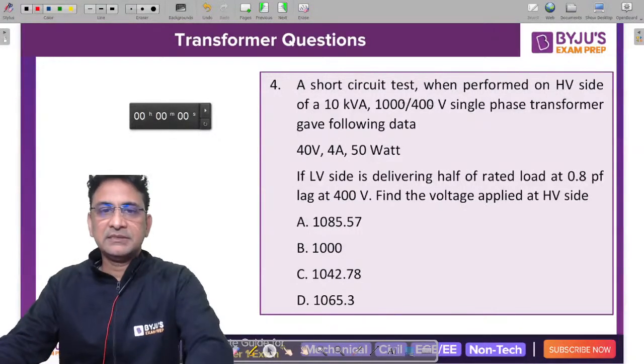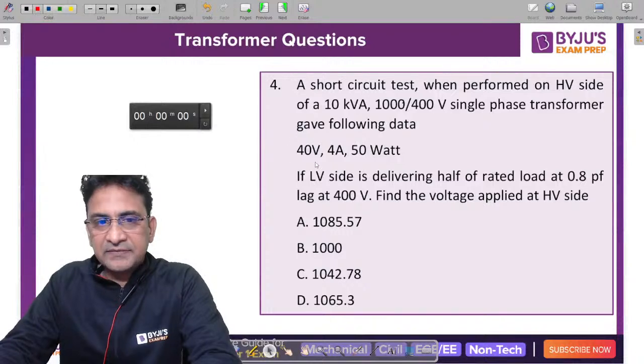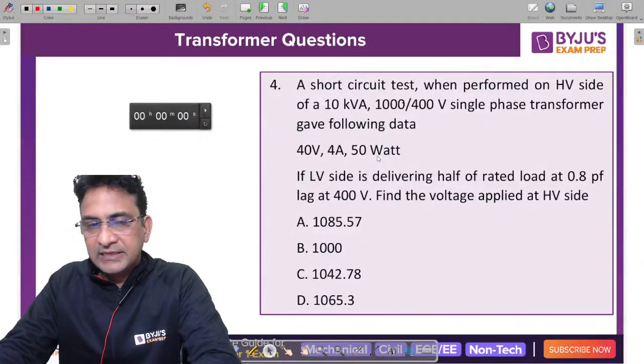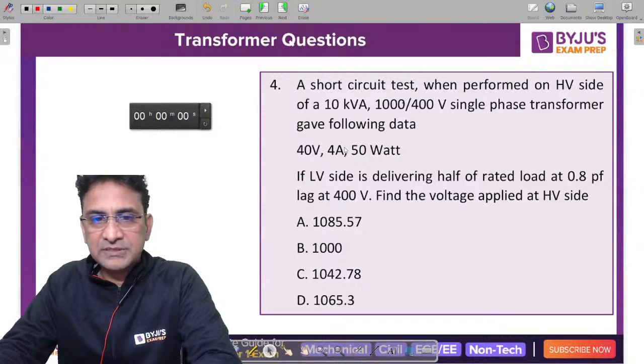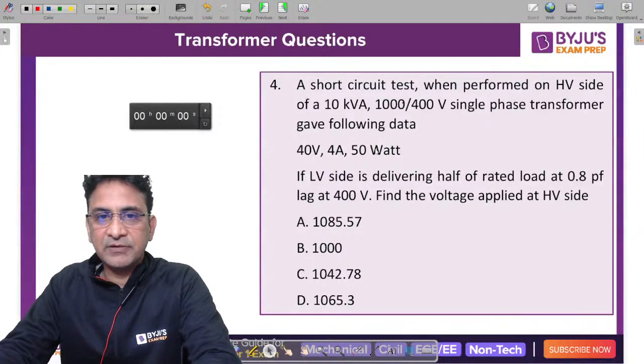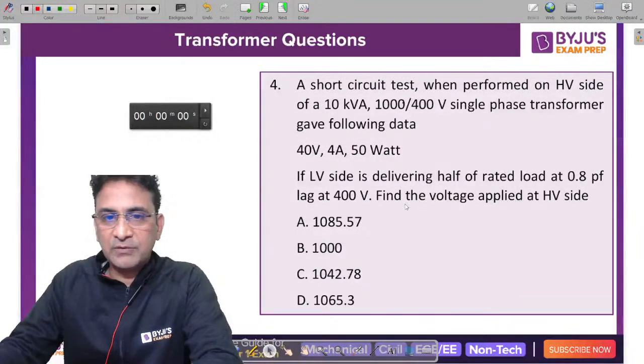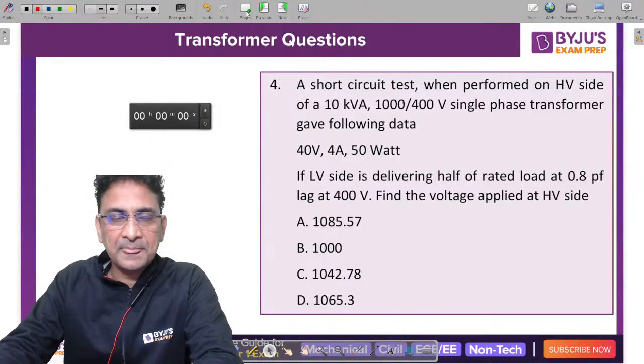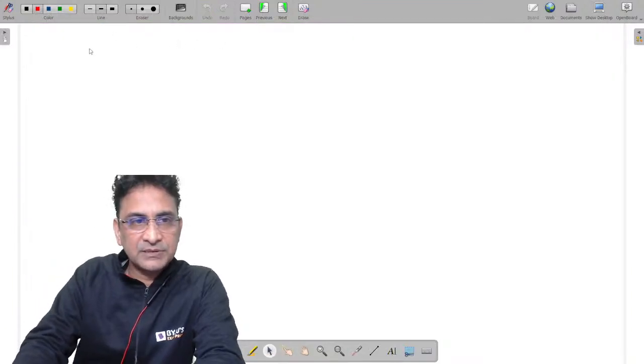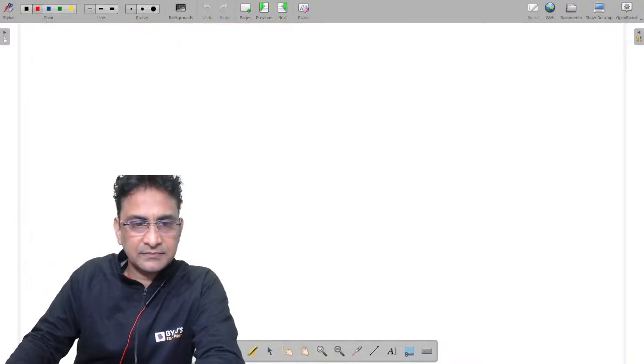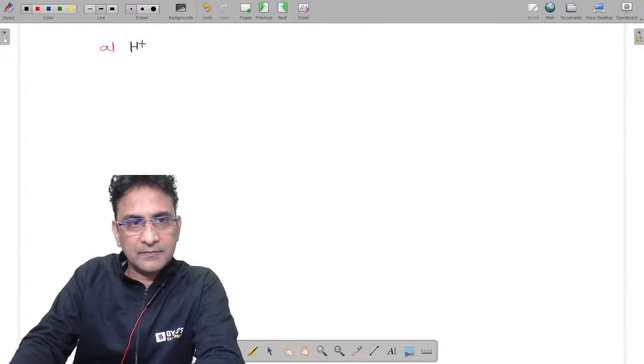1042.78. See, from the short circuit test data, we can find out the value of equivalent resistance and equivalent reactance. The short circuit test is performed on the high voltage side, so we get the equivalent resistance and reactance referred to the high voltage side. High voltage side is my primary winding and the low voltage side is my secondary winding. So at the high voltage side, we can find out the value of equivalent resistance.